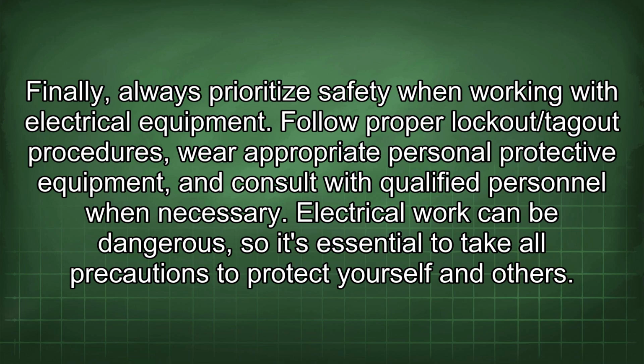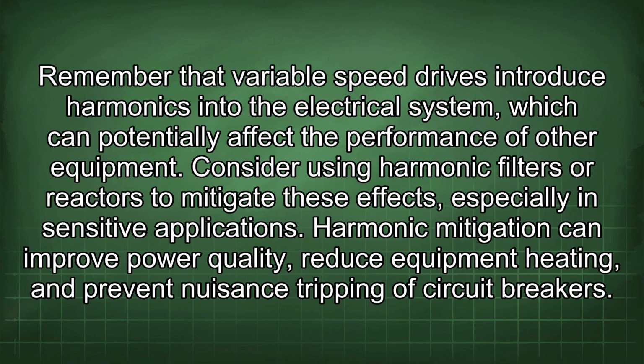Electrical work can be dangerous, so it's essential to take all precautions to protect yourself and others. Remember that variable speed drives introduce harmonics into the electrical system, which can potentially affect the performance of other equipment. Consider using harmonic filters or reactors to mitigate these effects, especially in sensitive applications. Harmonic mitigation can improve power quality, reduce equipment heating, and prevent nuisance tripping of circuit breakers.